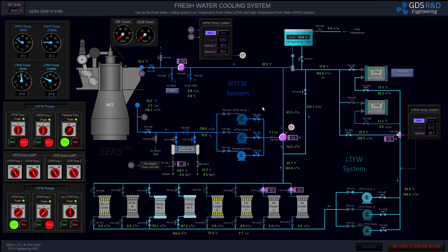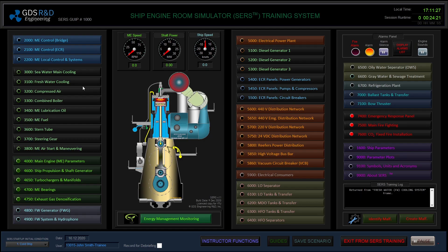The flow goes into the preheater and into the main engine. The high temperature fresh water controller is in manual mode — it is circulating some low temperature and high temperature fresh water and mixing at this valve. I will switch this valve position to zero, meaning the high temperature fresh water will be circulated in the loop so I can heat up the main engine faster.